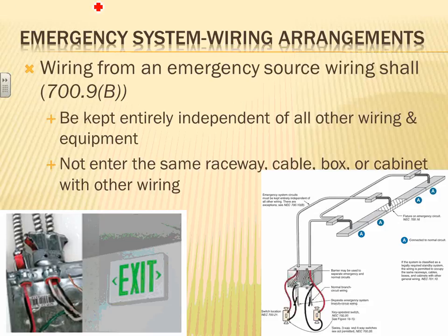Okay, so emergency systems wiring arrangement. Now, either we have two services, or you can have a generator. If we have a generator, we have to completely separate the emergency wiring system from the normal and the legally required standby system. Complete separation. Switches, receptacles, boxes, you name it. So kept entirely independent of any other wiring. They can't enter the same box.